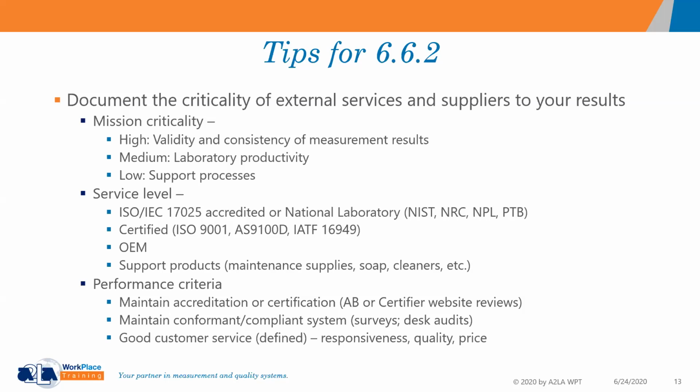Whereas, if it's a supporting process for your laboratory activities, maybe you don't have as stringent a requirement for the external provider of your products and services. And then another thing to look at is the service level itself. Do you want someone that's accredited, or someone that's just certified to ISO 9001, for example? The biggest difference between 17025 and 9001 is that 17025 is more of a measure of competence, whereas 9001 is more of a measure of just having a management system in place that the lab or organization is following. So there's a very big difference between the two of them.